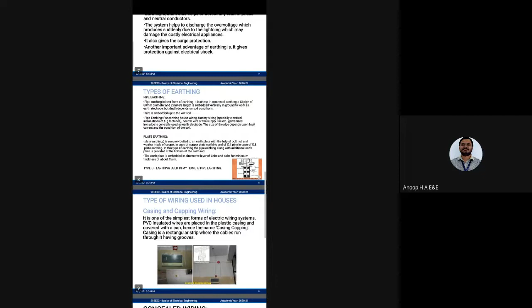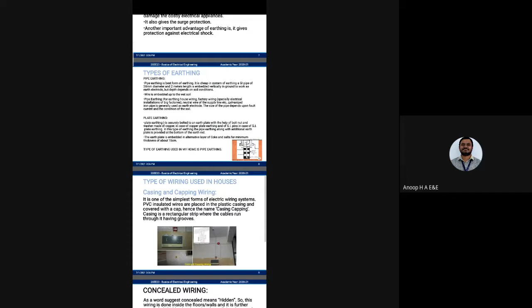Pipe earthing is used for earthing house wiring, factory wiring, special installations of big factories, and the neutral wire of the supply line, etc. Galvanized iron pipe is generally used as the earth electrode. Plate earthing: the earth wire is securely bolted to the earth plate with the help of a bolt, nut and washer, made of copper in the case of copper plate earthing, and of GI in the case of GI plate earthing.